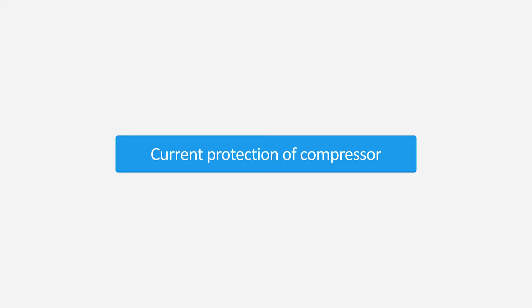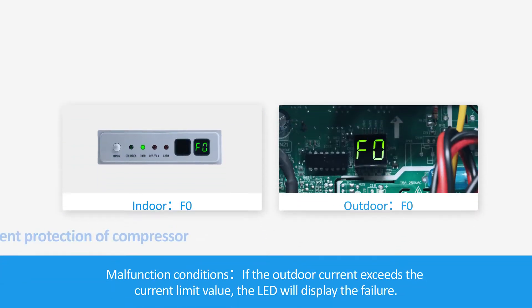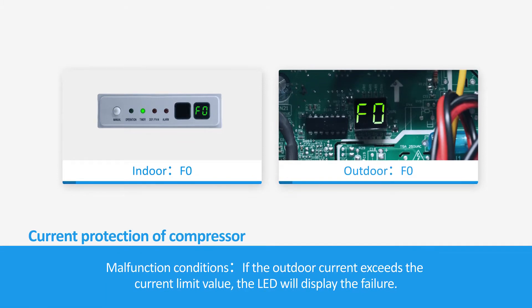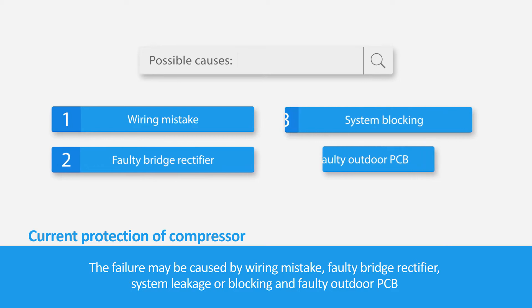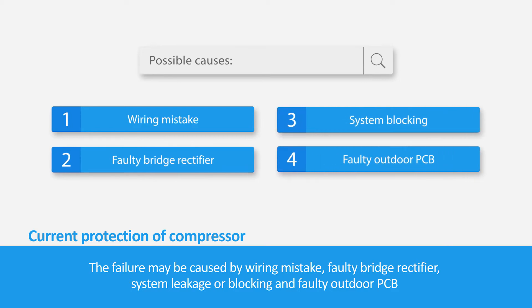Current protection of compressor. If the outdoor current exceeds the current limit value, the LED will display the failure. The failure may be caused by wiring mistake, faulty bridge rectifier, system leakage, or blocking and faulty outdoor PCB.